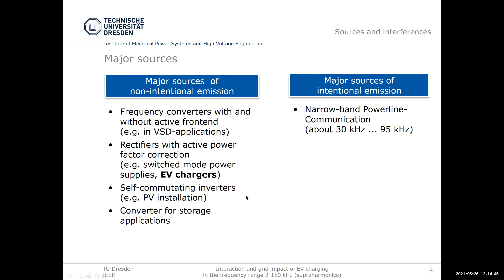Just to give you an idea about the different frequency ranges and how that looks in the supraharmonic range, here you see an exemplary measurement from a PV installation with a narrowband power line communication operating. And what is very typical in that frequency range is that usually the larger the size of a device, the lower is the switching frequency. So here we had about 9 large 100 kilowatt inverters. They had switching frequencies at 3, 6, and 9 kilohertz, for example. We had a bunch of small inverters below 10 kilowatts. They usually have switching frequencies in the range of 15 to 20 kilohertz, because it should be in a range where it is not audible, as they are usually, when it comes to rooftop PV, in the house.